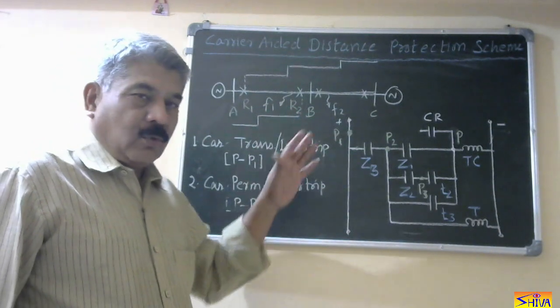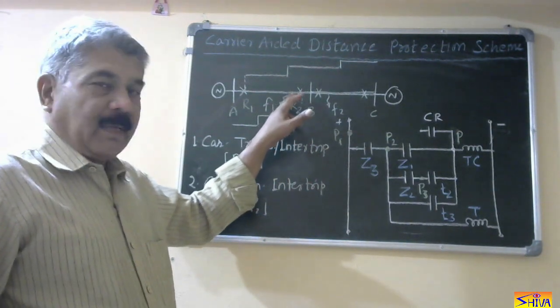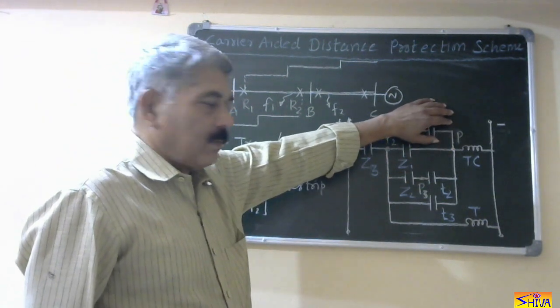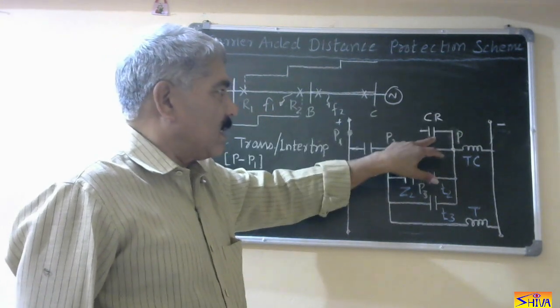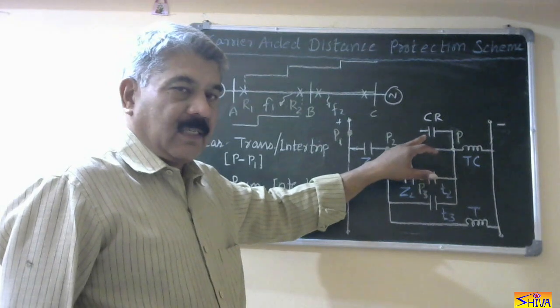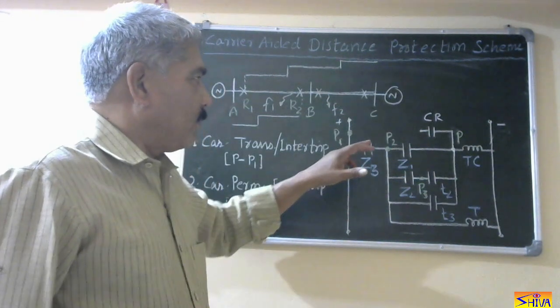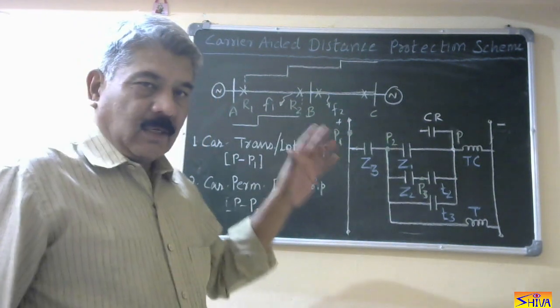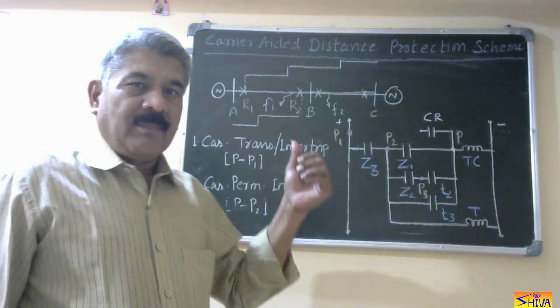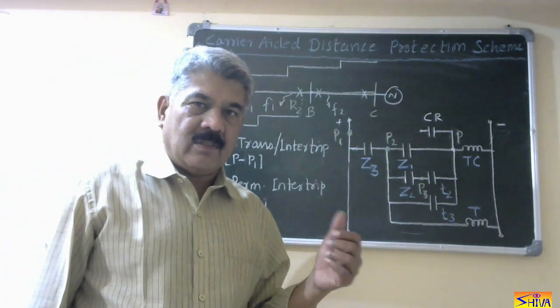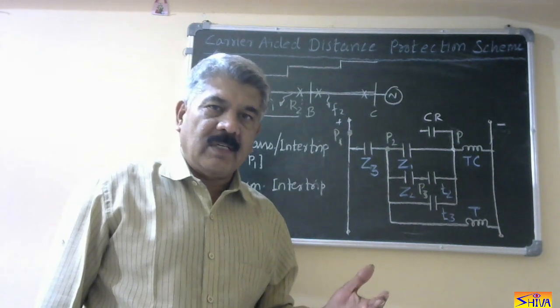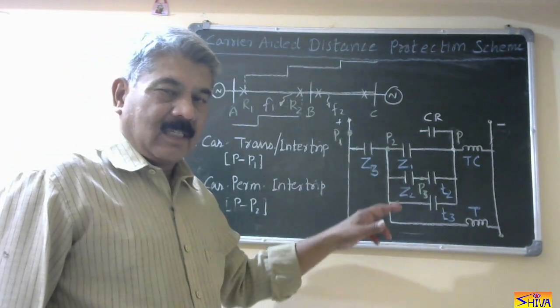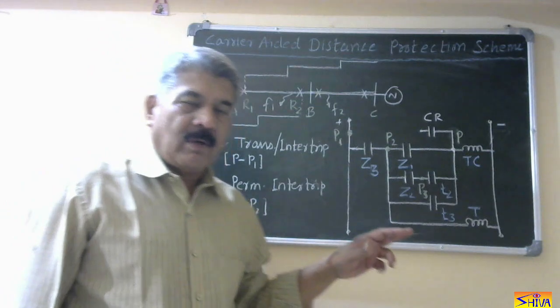If we do not use the carrier-aided distance protection scheme, F1 will be cleared in the second step. Now in this contact diagram, first we do not consider the CR contact — that is the carrier receive relay contact. If we do not use this contact, the scheme will be like this. We are assuming the relay has directional sense, so we are using a mho distance relay at R1 as well as R2. This is the contact diagram for a three-step distance protection scheme for a mho relay.